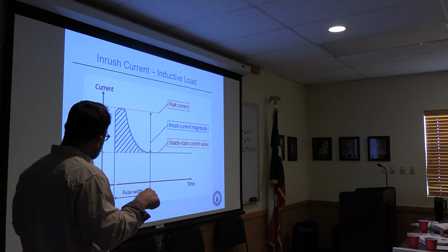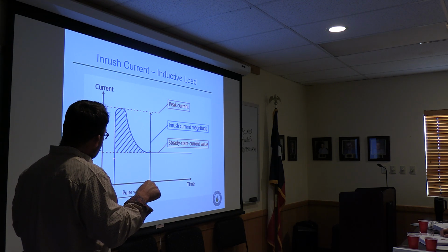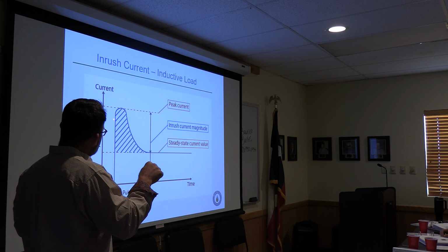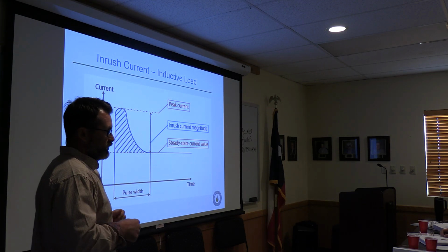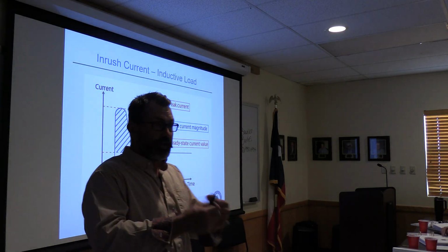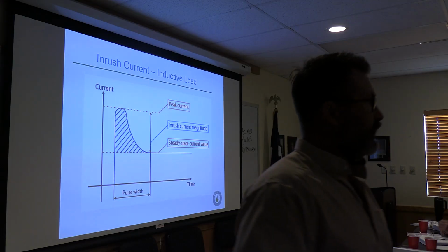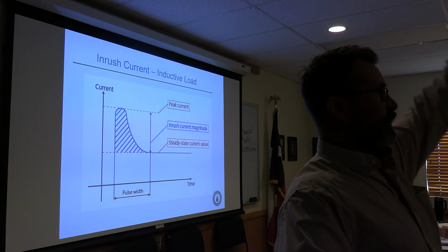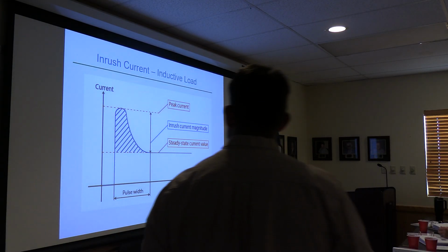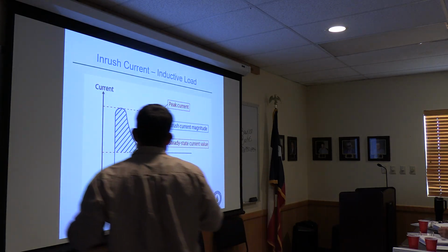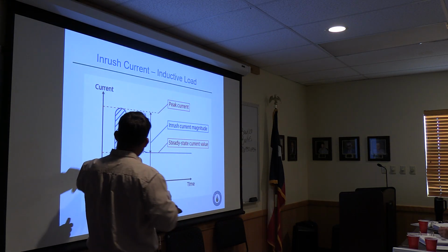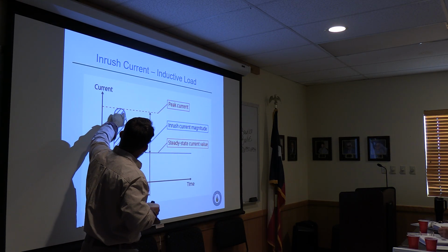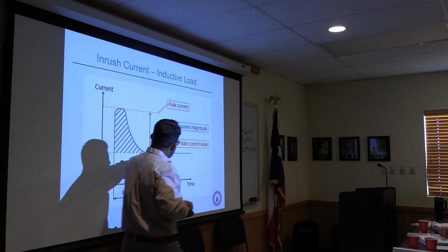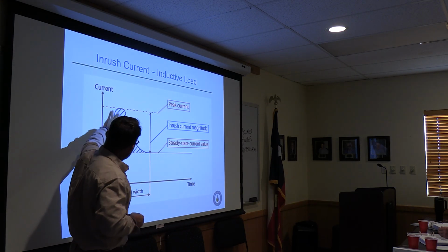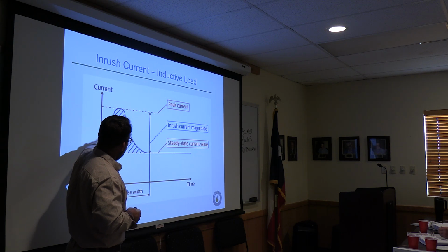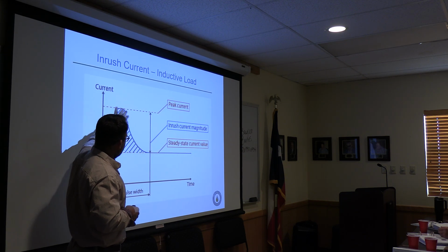Typically that first shot of electricity, by the math of it, it drives the current to infinity. Okay, just the way it works, because nothing's moving, there's nothing flowing. In an instant, that current level is trying to move to infinity because your volts have finally come online. At some point, the system catches up pretty rapidly, and you get a ramp that comes back down, and then you move to your steady state current. This shaded area under this inrush curve is basically burnt electricity.